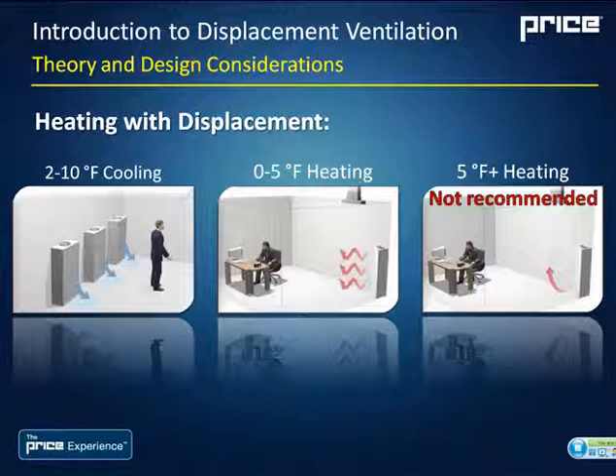If you're looking at supply temperatures close to room temperature or slightly above it, of about 5 degrees, the air is basically going to travel straight out from the diffuser at about a 90-degree pattern, and it's going to travel in sort of a wall across the room. It's not going to stick as tight to the floor because it isn't quite as dense, but you're still able to provide your ventilation requirements or a slight heating demand.